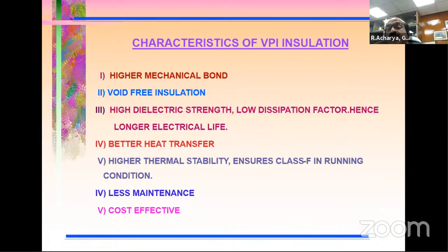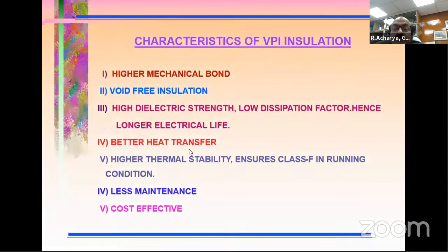That is another point wherein whatever heat is generated due to the I square R loss and all that has to be effectively dissipated out. That is possible only when an electrical insulation is also a good thermal conductor. That is the most ideal thing, and that is possible in the case of a vacuum pressure impregnation system. It requires less maintenance, and it is very cost effective.